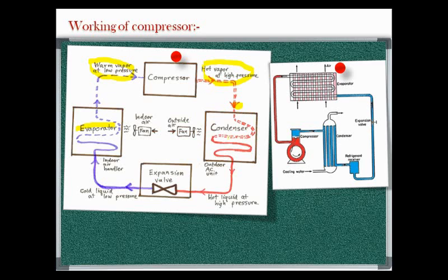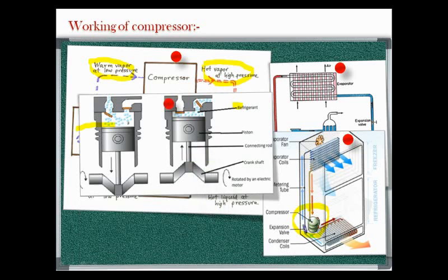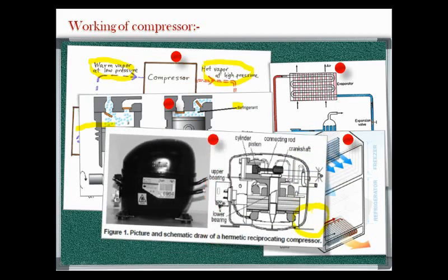The compressor is basically situated at the bottom part of your refrigerator. A reciprocating compressor is used to compress the refrigerant in a domestic refrigerator, and this compressor is hermetically sealed type. A hermetically sealed compressor is one in which the two halves are sealed by welding or brazing. The electric motor and reciprocating mechanism are placed inside this housing, where the piston moves within the cylinder for compression.